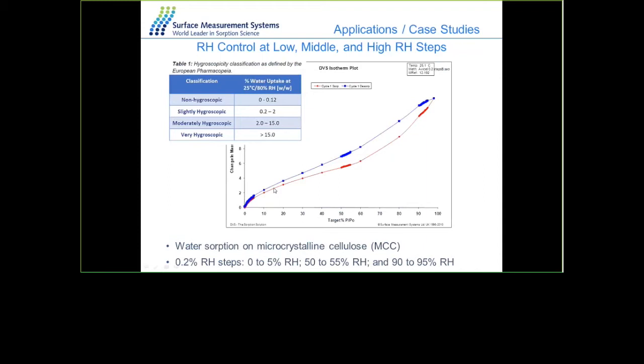Here is a classification table for hygroscopic materials. Very low levels of uptake — down to 0.12% — are classified as non-hygroscopic material. It is therefore important for the balance to register very low mass uptakes, and for the mass flow controllers to accurately control vapor concentrations.